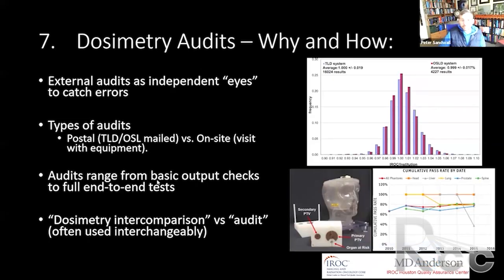So audits range from these basic output checks, which are essential, to full end-to-end tests using phantoms, such as this head and neck phantom from MD Anderson. So that dosimetry intercomparison, where you're using different equipment, versus an audit, those expressions are often used interchangeably. This is some data from MD Anderson, and it shows the variability. This is from 16,000 different dosimetry audits. A large range of people are within plus or minus 5%. But there are some cases that are as much as 10%.